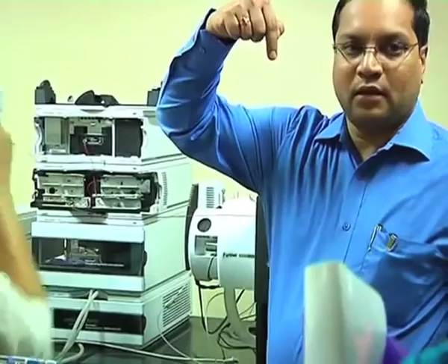So it goes in, and as you see, what is the output here? It's a stream of liquid. But what does it measure? Mass, ions. So the language being spoken is not understood by this right now. So we need some sort of device which converts this liquid into ions. That is the role of an interface, which is also called an ion source or atmospheric pressure ionization technique, and one type of atmospheric pressure ionization is electrospray ionization, which is this. Electrospray ionization, or more properly called pneumatically assisted electrospray. Why so? It is something called a spray. So the stream of liquid goes into the needle, and then it is sprayed.